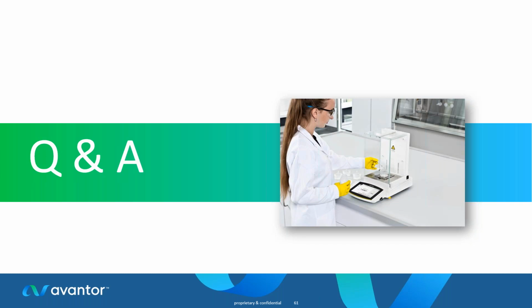Well, I'm guessing that you're not in a highly regulated environment, but as I mentioned before, most balances will have internal calibration on them. So a good tip is also to always do an internal calibration on the balance as soon as you've moved it. Let it acclimatize. Once it's acclimatized, perform an internal calibration on there. Also check the balance with your external traceable weights and make sure that the balance is within tolerances. If you do this, this gives you a certainty that the balance is in calibration, it's been readjusted, and you should be good to carry on.